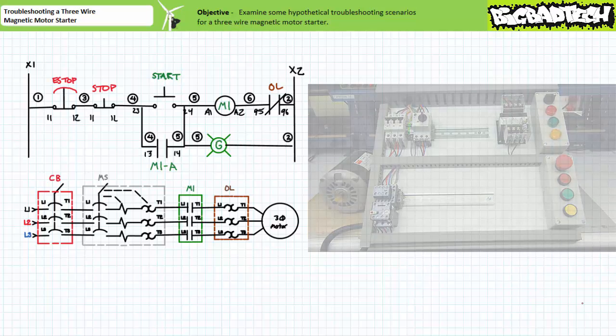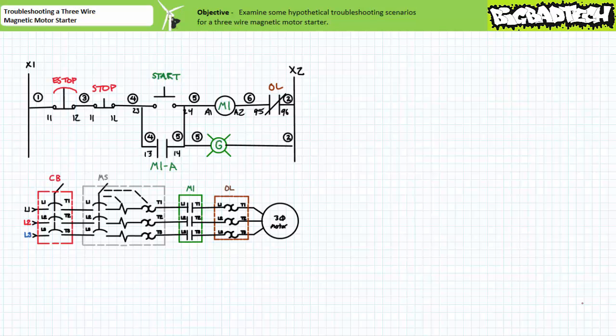Low or no-voltage protection circuits like this one are commonly employed in scenarios where an operator may be injured or an industrial process damaged by the unexpected restart of a motor. Let us now explore the limitations of low or no-voltage protection. Low or no-voltage protection circuits necessitate the pilot holding circuit dropout for this feature to function. If power is restored to the whole system the moment an operator happens to be pressing the start button, this system could still suddenly restart, as would an ordinary two-wire control circuit when the automatic input is still being triggered. By no means are these systems foolproof. And given the large population of fools you work with, you must take necessary precautions when working on systems where your safety is of primary concern. For this reason, lockout and tagout procedures are vitally important.